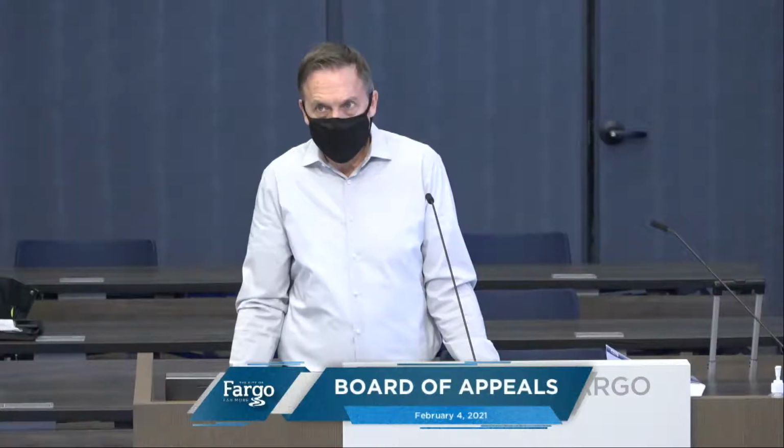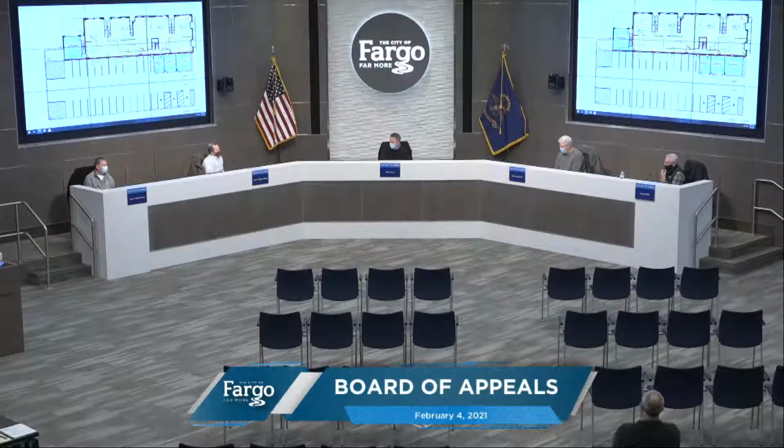Bruce, can you talk about continuity just a little bit? How do you interpret a fire barrier and continuity with a fire barrier? Because it seems like the big issue here is that nobody's arguing the fact that there are fire barriers required between these units. The real issue is that a fire barrier is extending out between the units, but there's no continuity. In theory, you could have a fire that starts on one side of that wall in the corner, and there's nothing to stop it from going around the corner and getting to the other side. So I think continuity is an important part of that discussion.